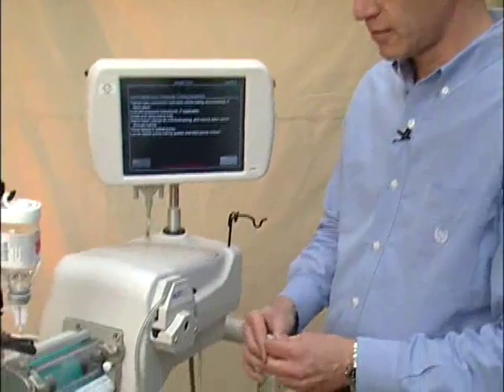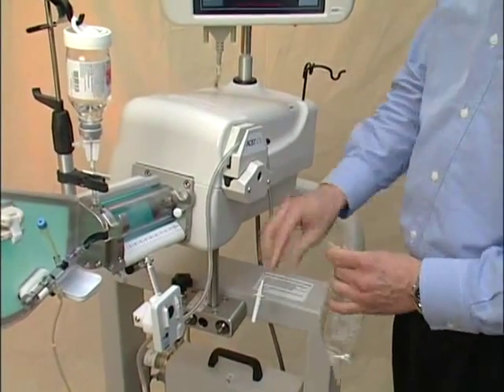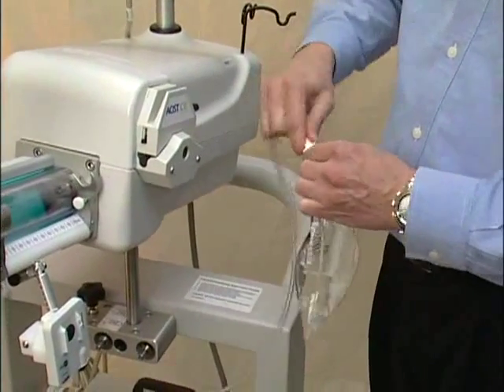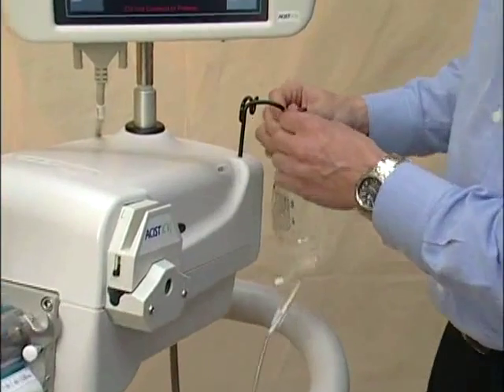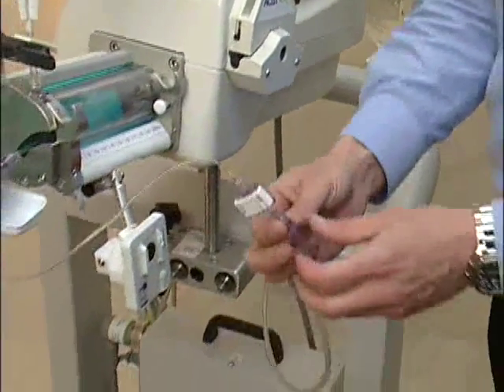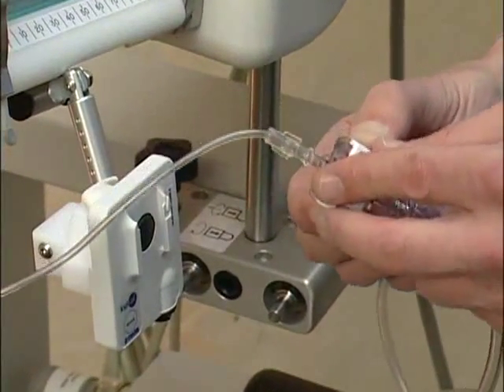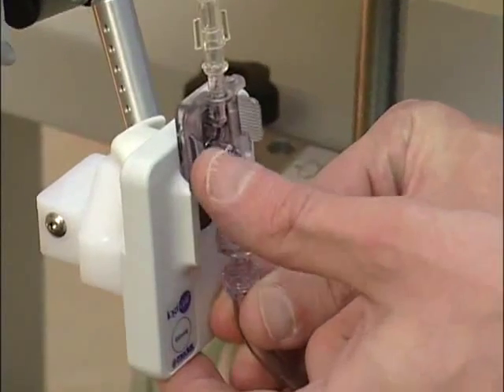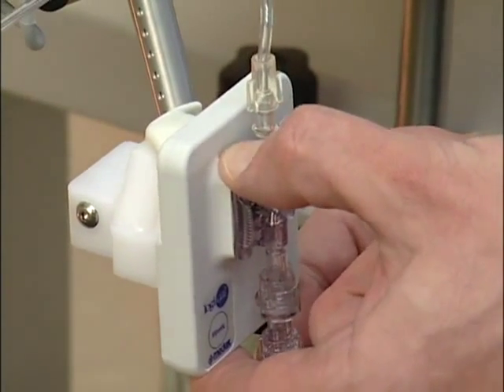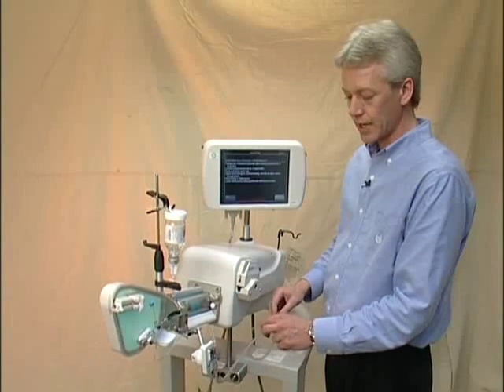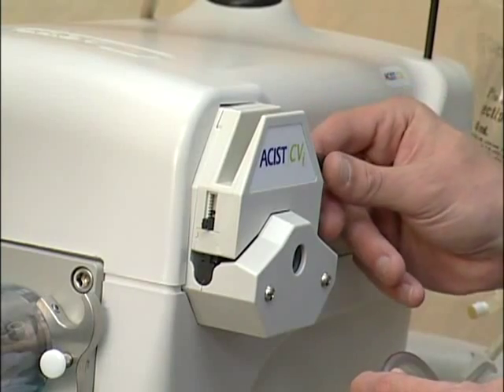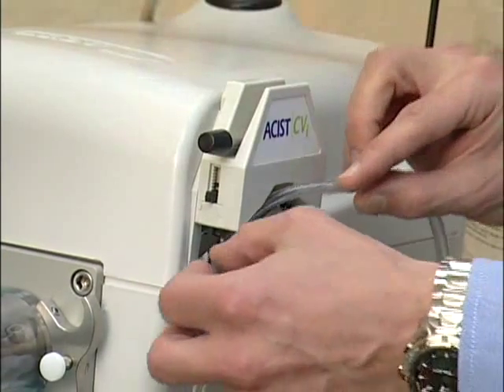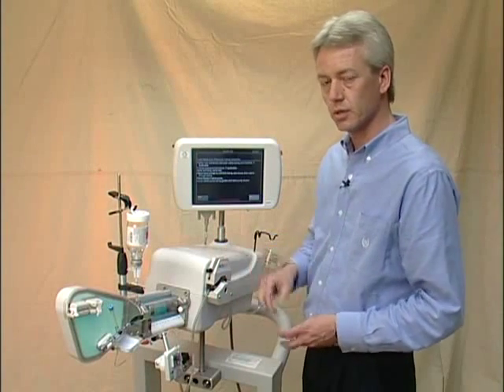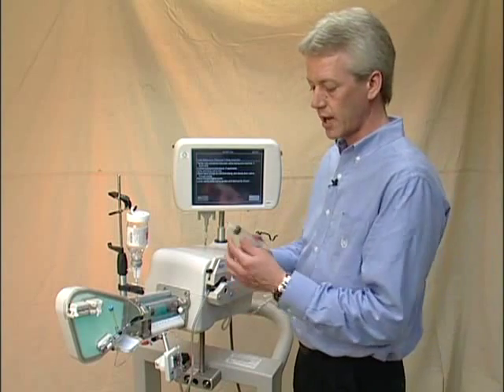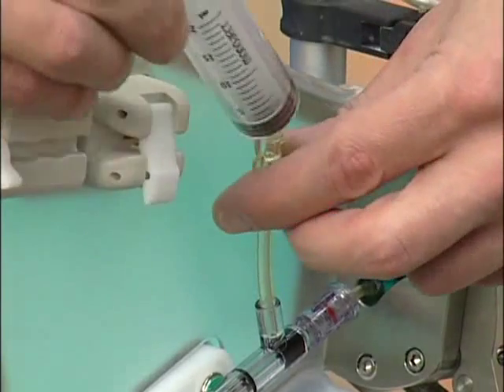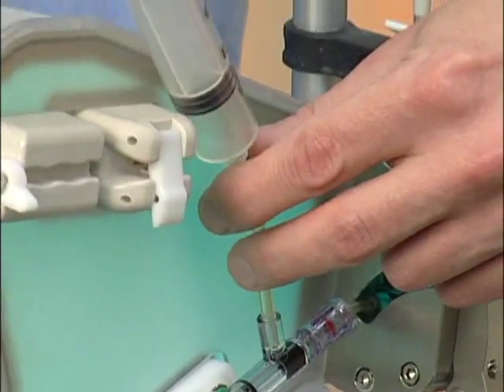For the setup of the saline line, I'll spike my saline bag and hang it on the hanger provided in the back of the system. I'll remove the protective cap on our transducer cartridge, which then allows me to insert this into the MEDX transducer. Verify that you do hear a snap and that it will be fully engaged in the transducer. Once that step is complete, I'll put my tubing in the peristaltic pump by lifting the latch that allows me to insert the tubing. But before we latch that closed, we're going to draw back saline with our hand syringe from the manifold area. I'll attach the hand syringe and slowly draw back saline to wet the tubing.